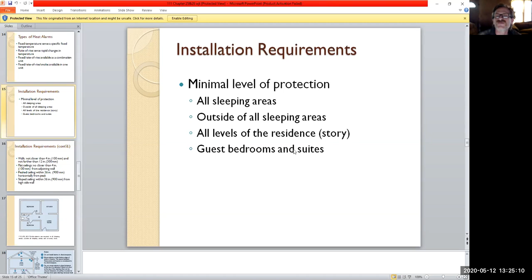There are installation requirements for height. You can have them on a wall, but they have to be more towards the ceiling, because heat rises, smoke rises. With respect to the ceiling, if it's on the wall, it can't be further than 12 inches away from the ceiling - that's how far down the wall - and no closer than 4 inches up. The reason is for airflow.